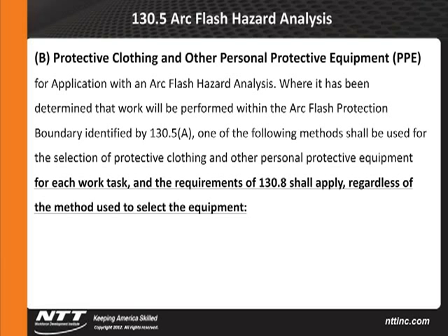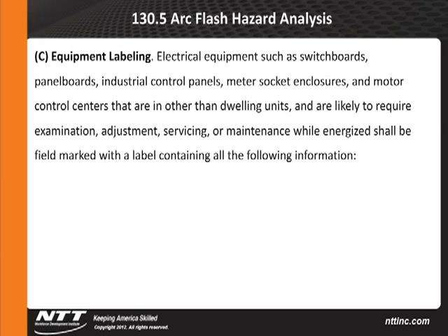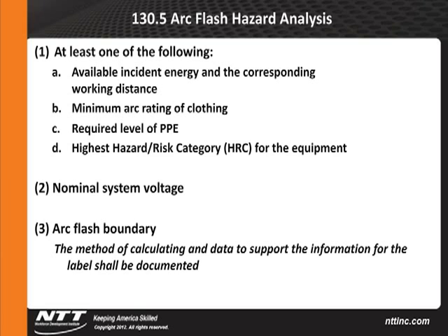Equipment labeling. Electrical equipment such as switchboards, panelboards, industrial control panels, meter socket enclosures, and motor control centers that are in other than dwelling units, basically housing, and are likely to require examination, adjustment, servicing, or maintenance while energized shall be field marked with a label containing all of the following information. And this is some new language. At least one of the following has to be done: the available incident energy and the corresponding working distance, the minimum arc rating of clothing, the required level of PPE, or the highest hazard risk category for that equipment, regardless of the task being done.